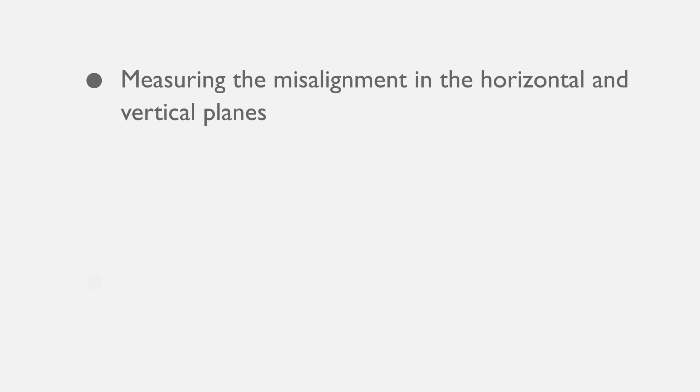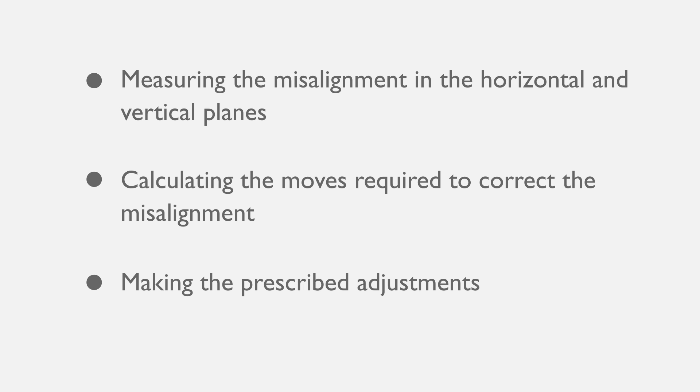The challenge of precision alignment can therefore be defined as first, measuring the misalignment in the horizontal and vertical planes, second, calculating the moves required to correct the misalignment, and finally, making the prescribed adjustments.